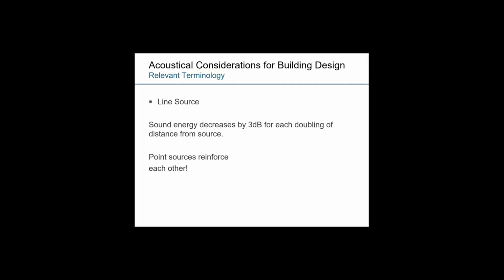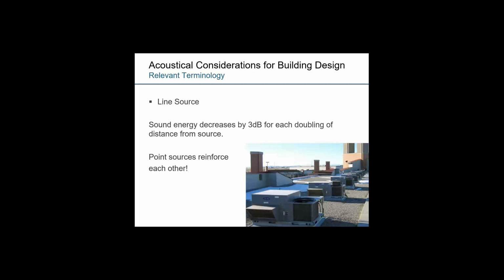Another thing with sound and sound transmission is looking at sources of sound and how sound transmits from a source. When we look at a line source, we often look at multiple sources that would reinforce each other. Something like this here, where there are multiple rooftop units added in series along a certain length or span. And the more sound sources that might be present, the more sound energy could transmit outwards from it.